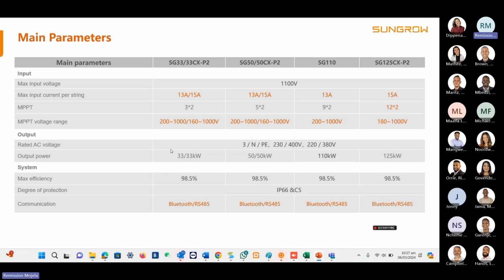And then the rated output power of these systems is 33, but all of our inverters have a 60% reactive power production capability, which will change the rating of the inverter to a kVA rating. It will still be a 110 kVA, but it can produce up to 60% of reactive power while dropping the active power to 40%, depending on how you want to utilize it. All of these devices are capable of that. Then they have built-in communication of Bluetooth and RS-485. To communicate directly to the inverter, you can use the iSolar Cloud via Bluetooth. And to control the inverters, it has to be Modbus RTU, basically an RS-485 connection to the inverter from the controller that you want to use on the system.